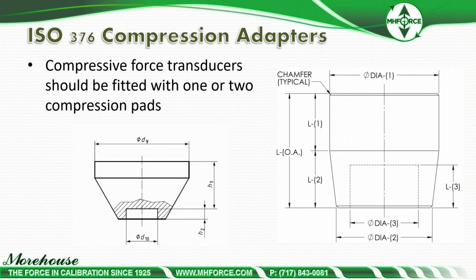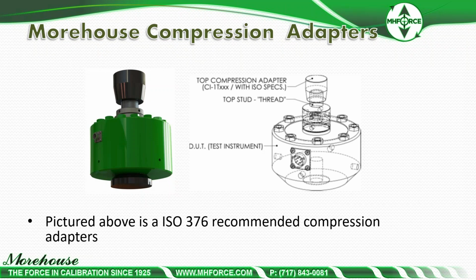We were talking about ISO 376, and this is from the standard. It says a compressive force transducer should be fitted with 1 or 2 compression pads, and that's what we're looking at here, with the standard to the left and some of our products to the right. If we look at this in more detail, what does this look like? This is a recommended setup for ISO 376. It's a bit different than what people normally see if you're not accustomed to the standard, because they are calling out base plates and top adapters.